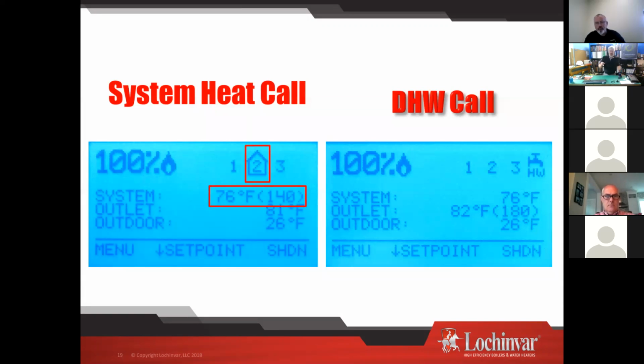Priority is not a great term, but it is a temperature priority, okay? Because the boiler's not controlling pumps other than a system pump and a domestic hot water pump. But the highest water temperature will always get priority. So keep in mind, if you say, hey, I'm going to put my radiant on here and I'm going to put my hydro air on here, your radiant will still need some sort of thermostatic mixing valve to protect it in the event of a higher temperature demand. So just keep that in mind.